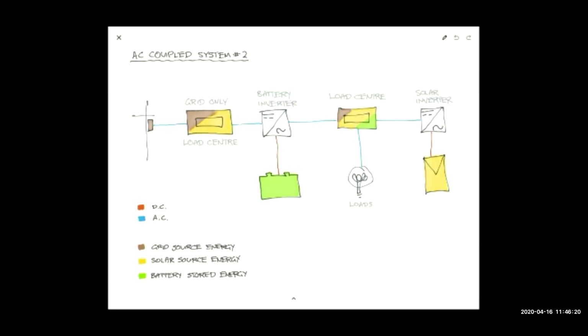You'll notice I talk about a grid-only load center. That's kind of optional, but you may choose that some circuits aren't critical to be backed up. For instance, maybe your hot water service, a large resistive element, or a swimming pool pump that doesn't have to run all the time. So you may have some loads that automatically drop out when the grid fails. Whereas critical loads, we'll call these critical, you want these to be powered during grid outages. So this is your critical load center.